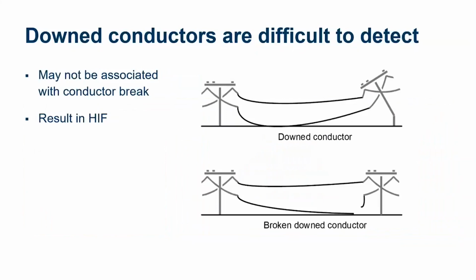Now, that is probably the most common condition to having a down conductor, but we can also have conditions where we have, let's say, a broken cross arm or some other damage to our pole or conductor carrying infrastructure that allows our conductor to make contact with the ground or make contact with something that is in contact with the ground while still being connected to downstream load.